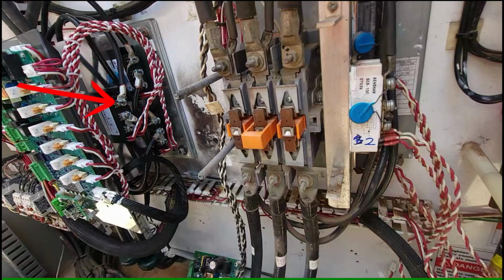So this is one form. This is probably the more common form, especially on smaller equipment. So what we're doing here is we have these SCRs, and in this particular application, we want to use these SCRs to slowly apply power to the motor, so that instead of having a huge inrush of current at start, we gently apply power to the motor to allow it to slowly come online.